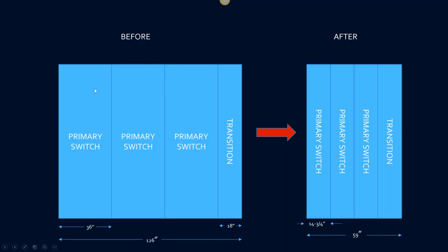We took 3 sections of metal enclosed primary switchgear plus the transition section, which came out to be about 126 linear inches. And we converted all that with the same functionality, actually more functionality, with the integral grounding switches. And I believe these also include live line indicators. Is that correct, Mike? Yeah, they're available with both line and load side indicators, but this is key. Those line and load side indicators are rated for supplemental verification, so they're useful, and I do use them. But we need to be clear that does not replace absence of voltage verification, again, as required by Article 120.5 and NFPA 70E. Okay, great.